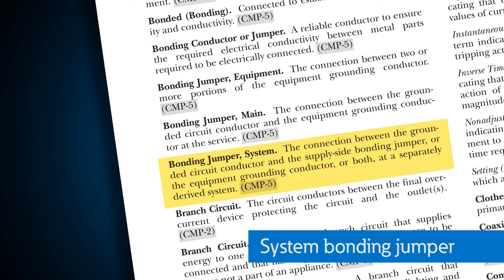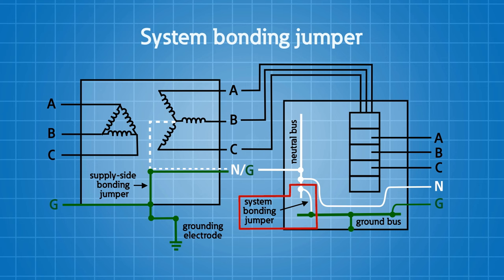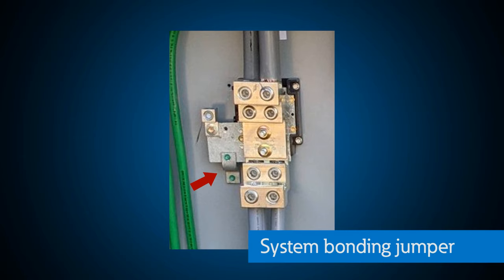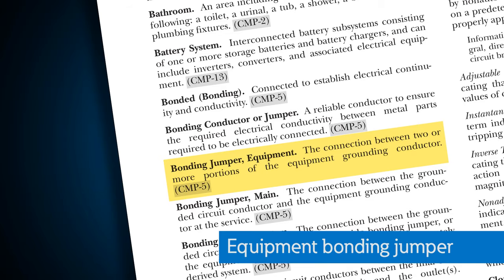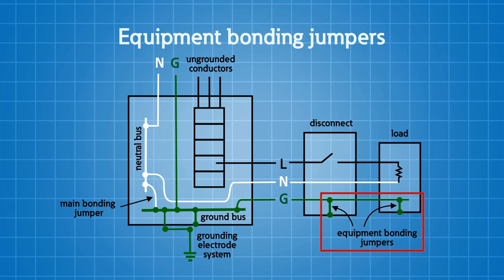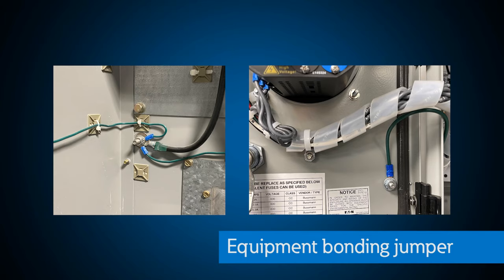Let's talk about the system bonding jumper: this is the connection between the grounded circuit conductor and the supply side bonding jumper. We have a grounded circuit conductor, we have a system ground where we're establishing our ground, and we need to bond those two together — that's what the system bonding jumper is. Your equipment bonding jumpers are the connections between two or more portions of the equipment grounding conductors, ensuring that everything is bonded together and that any jumpers between your equipment grounding conductor and the steel that needs to be bonded are properly in place.